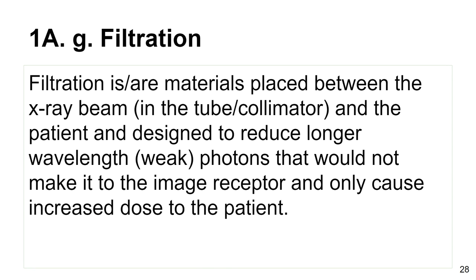Filtration is designed opposite to grids in terms of patient exposure — it's about saving radiation to the patient. Filtration will eliminate some of the longer wavelength, weaker beams that would not really affect the image or subject contrast negatively. That's all there is to say about filtration — it's a good thing.